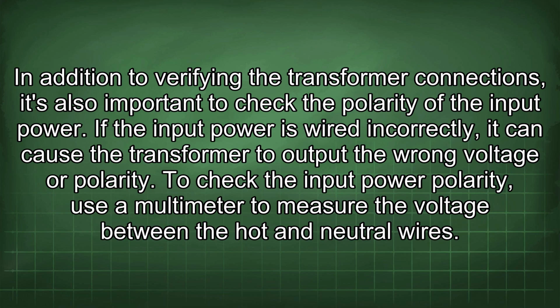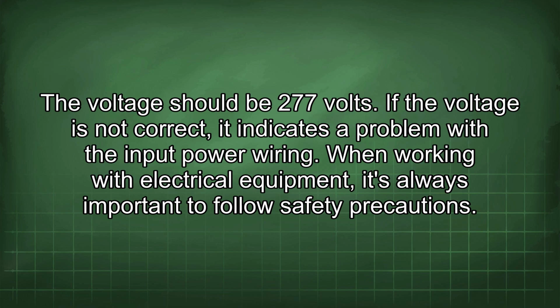In addition to verifying the transformer connections, it's also important to check the polarity of the input power. If the input power is wired incorrectly, it can cause the transformer to output the wrong voltage or polarity. To check the input power polarity, use a multimeter to measure the voltage between the hot and neutral wires. The voltage should be 277 volts. If the voltage is not correct, it indicates a problem with the input power wiring.